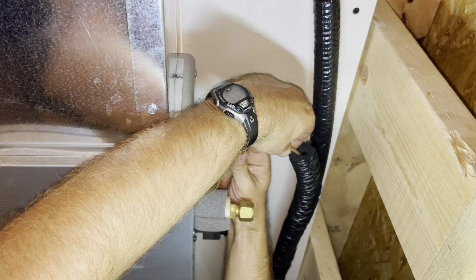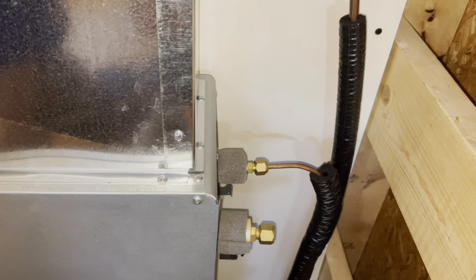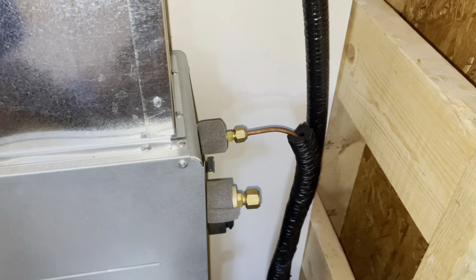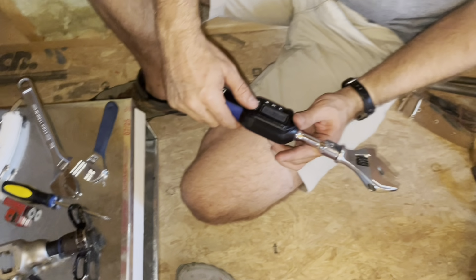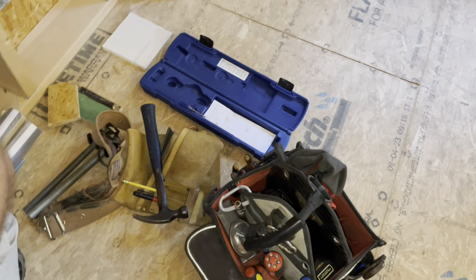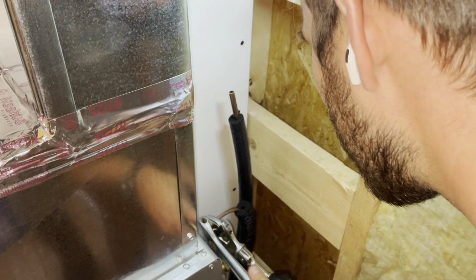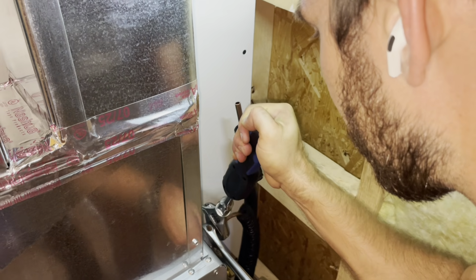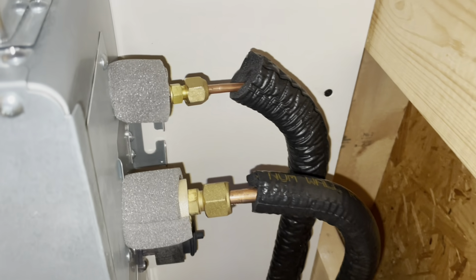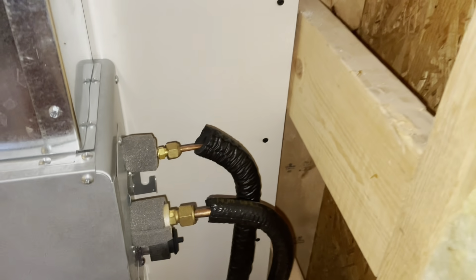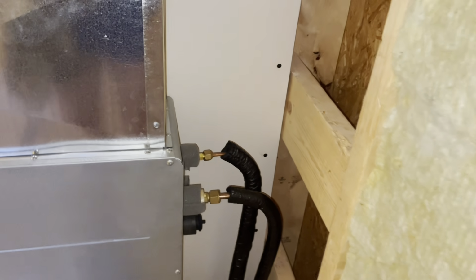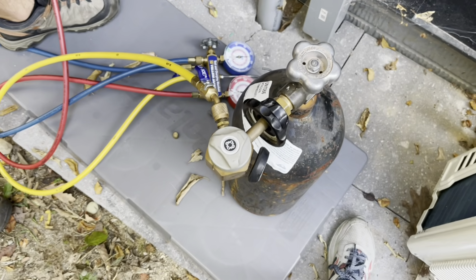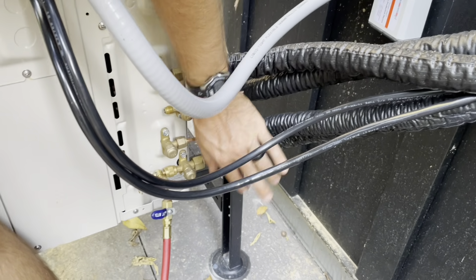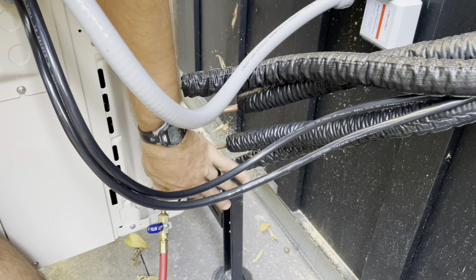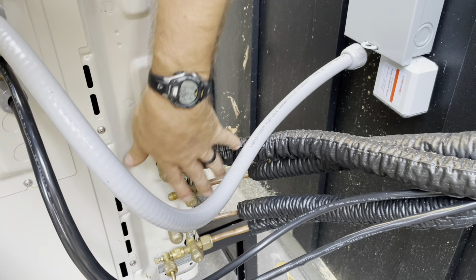Too hard of a material? You would know. 1/4 inch. I torque that to 11.8 foot-pounds. All done. Just have to hook up the thermostat wire somewhere. Aaron's currently pressure testing with nitrogen to make sure all the line sets are good. 400 psi, and these two right here. This one's not pressurized because they're separate.